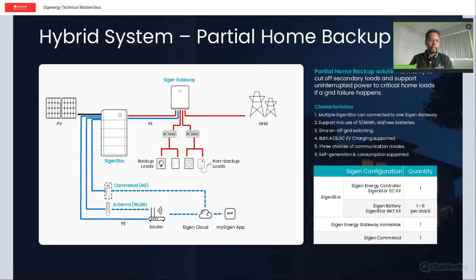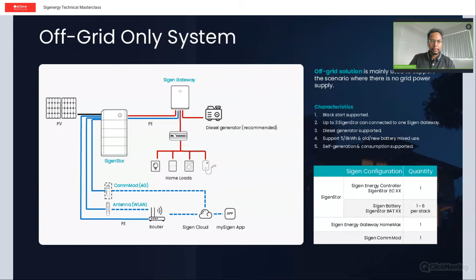You can do pure off-grid only. Again, it's exactly the same setup. For off-grid, you must have the gateway, and it's exactly the same setup. You just don't have the grid input. There is a generator input, again, into the smart port. For customers that have genset, they want to have an input. The smart port is already pre-built in the gateway. They can connect the generator. The generator can also go into the grid port in this case. There is a small setting under gateway settings that you just need to click and choose that the grid port is where the generator is coming from.